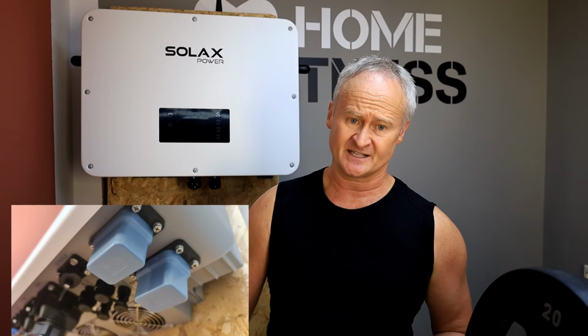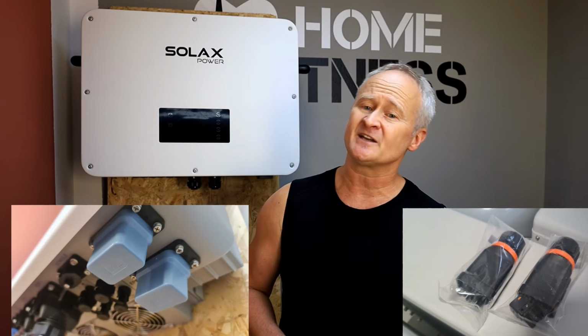Next, let's take a comprehensive look at the AC connections of the new Solax X3 Ultra inverter. Thankfully, we no longer have those terminal blocks, like on the X3 G4 hybrid inverter, where quite a few people probably let slip a few choice words when connecting the 6 square millimeter cables. Instead, as it should have been all along, we now have proper connectors that can even accommodate 16 square millimeter cables. However, always size the cable cross sections according to the specific conditions on site.